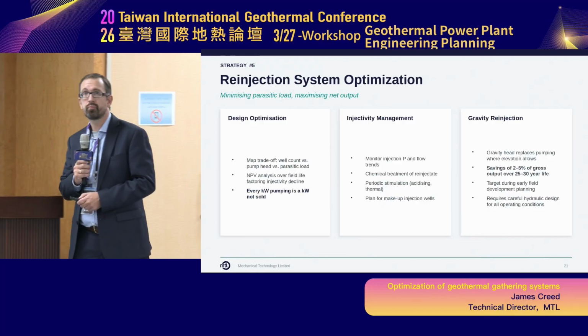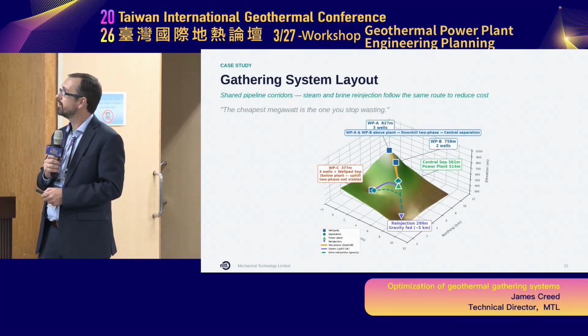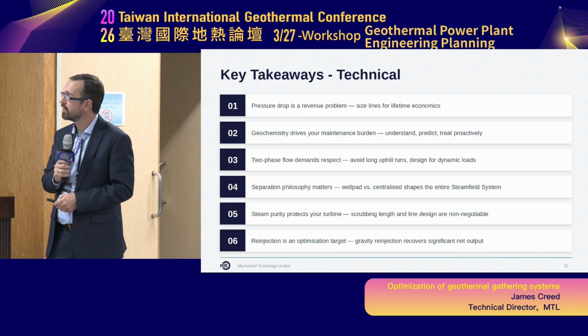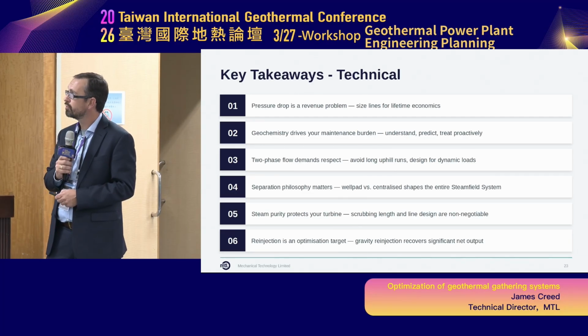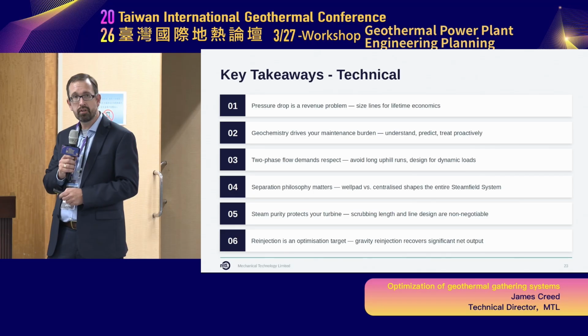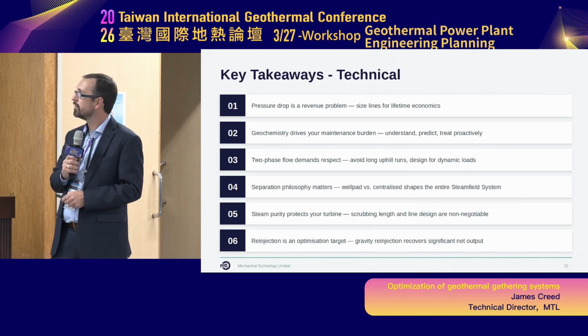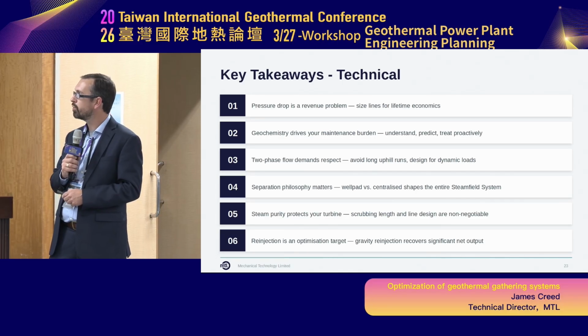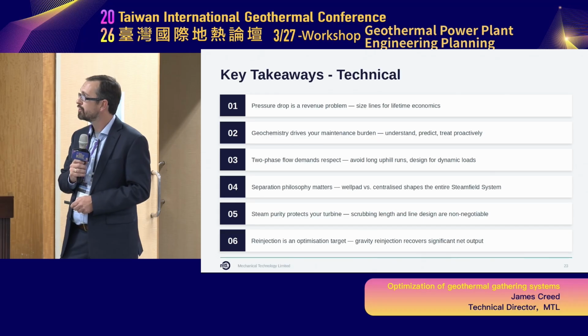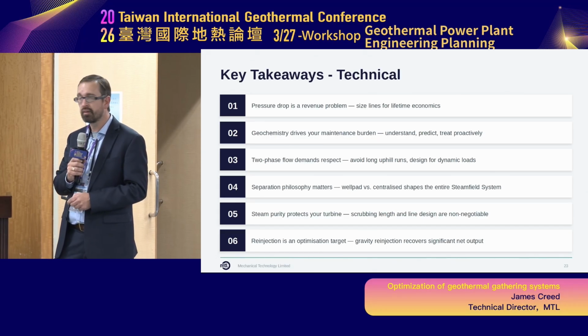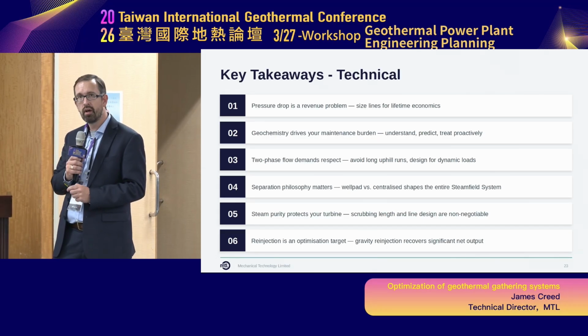I'll skip to the end to talk about key takeaways. Pressure drop is a revenue concern, so we need to size our pipelines and projects for the lifetime of the economics, not just day one. Geochemistry drives your maintenance burden, so we must understand it and proactively treat it. Two-phase flow demands respect—the forces it can generate are large.